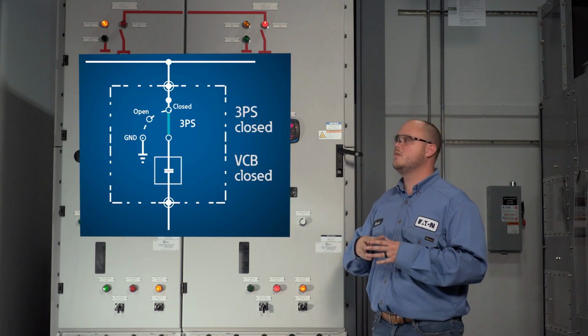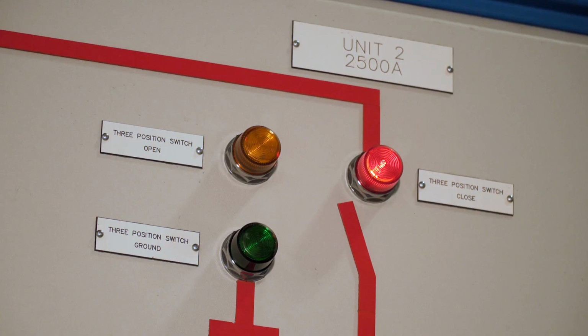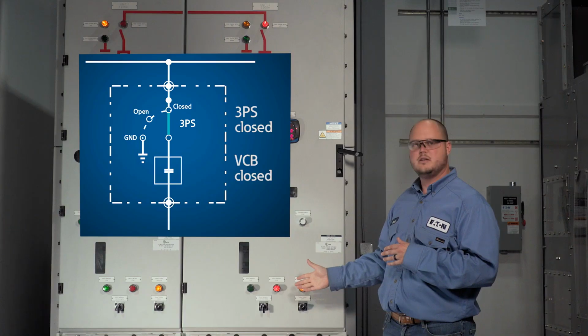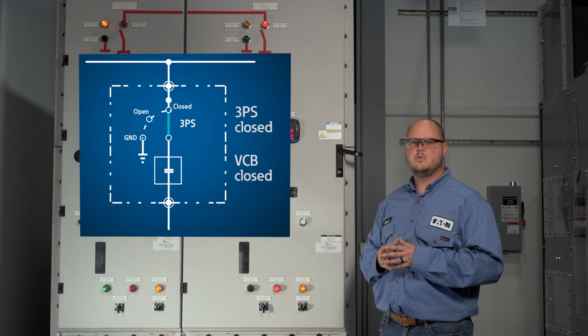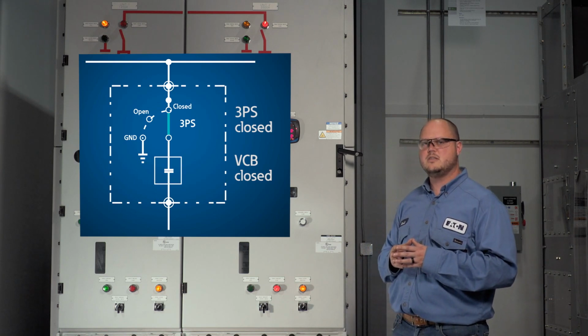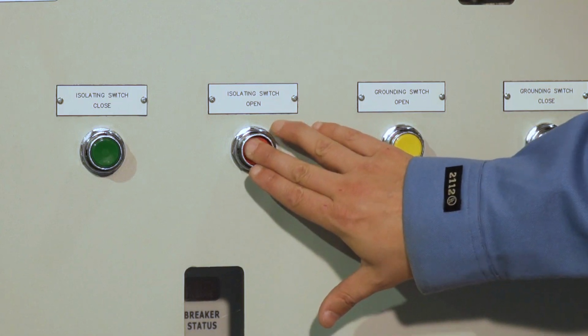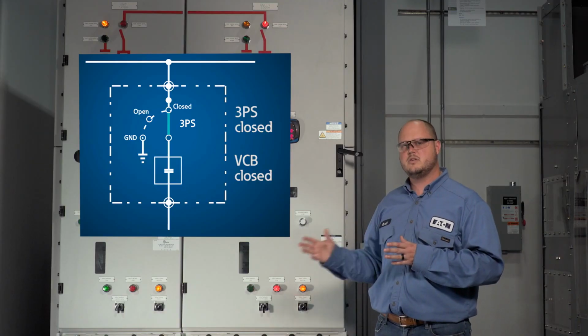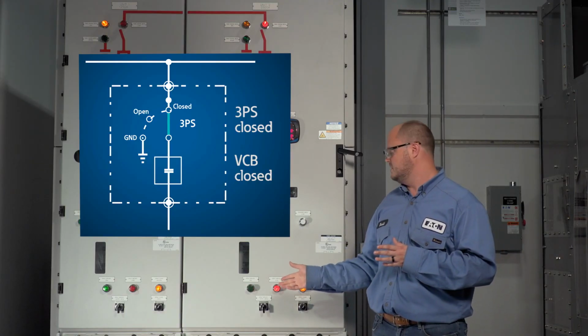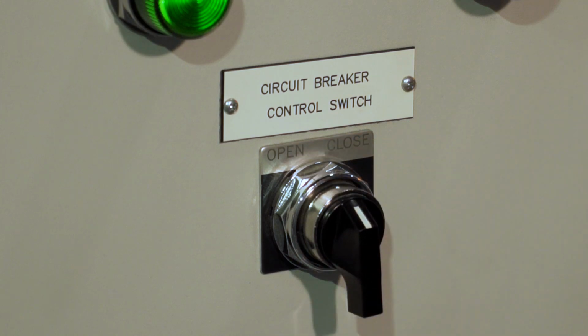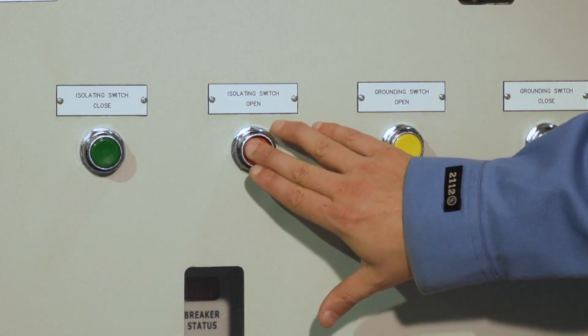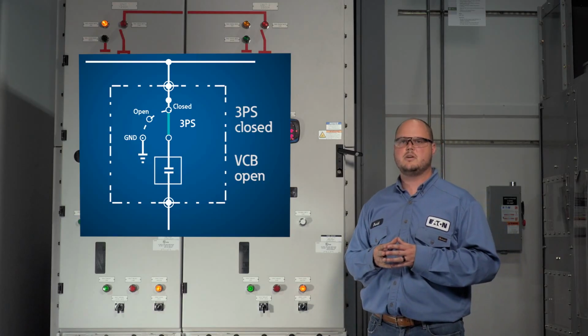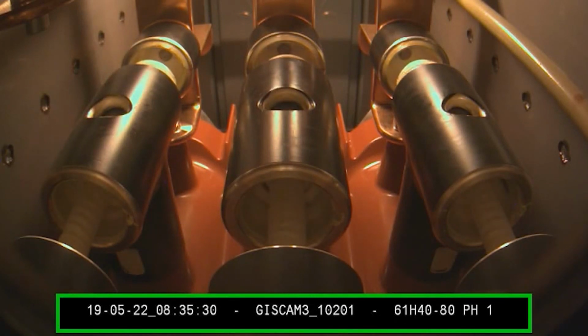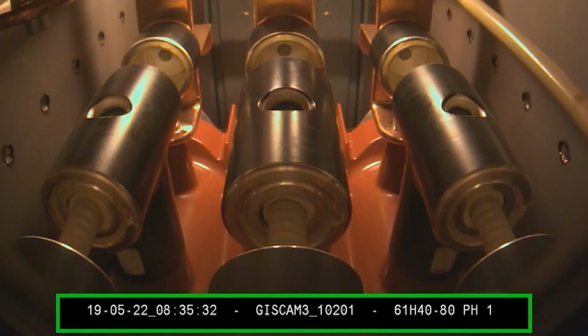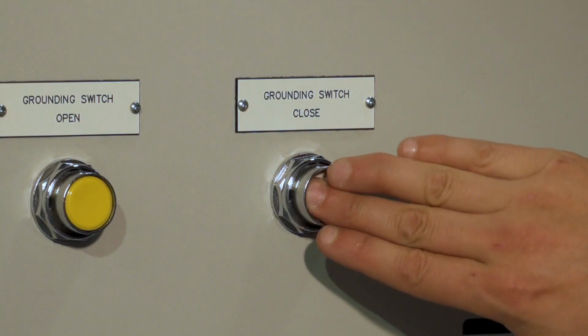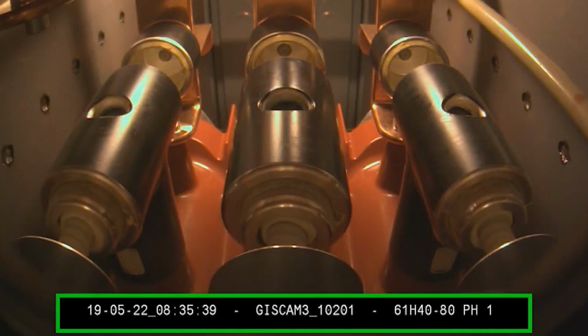We see now that the 3-position switch is in the connected position and that the circuit breaker is closed. If I try to move the switch to the open position, you can see that the switch does not operate. I will now open the circuit breaker, which allows us to operate the 3-position switch. Using the push button controls, you can see now that the 3-position switch can be moved to the open position and then to the grounded position.